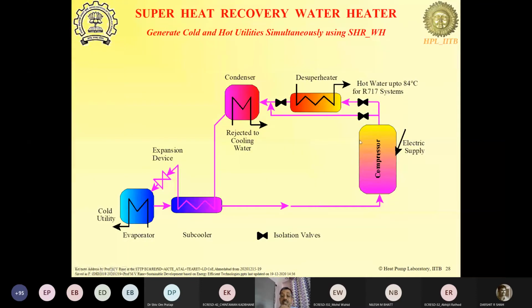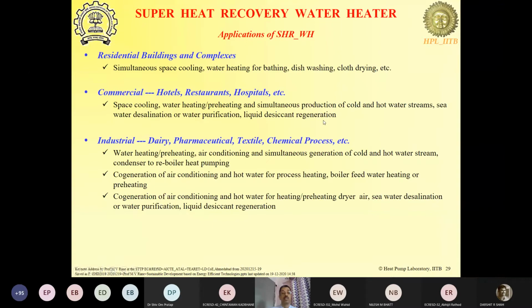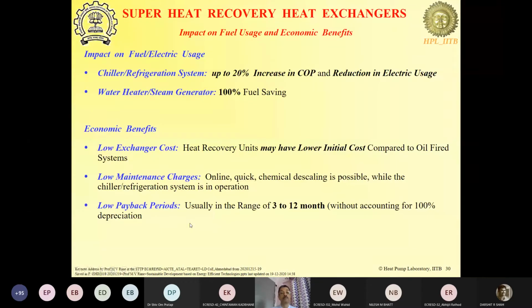So superheat recovery, basically after the compressor, the vapors are quite hot and we can recover. Like in the ammonia case, the vapor could be anywhere between 100 to 115 degrees centigrade, or at times even higher. So we had recovered hot water right up to 84 degrees centigrade in an ammonia dairy installation at Worli. Superheat recovery can find applications in residential, commercial, industrial applications, and can be used for many different applications as we have just discussed.